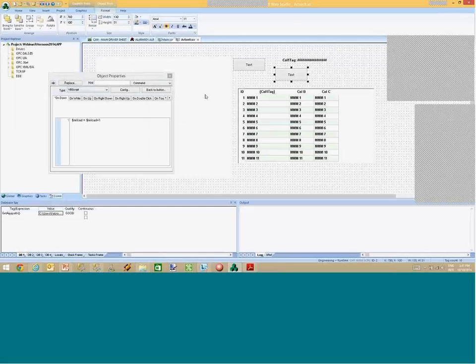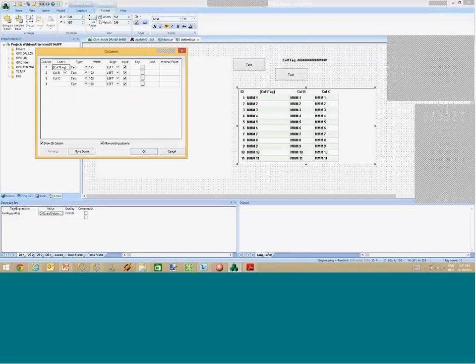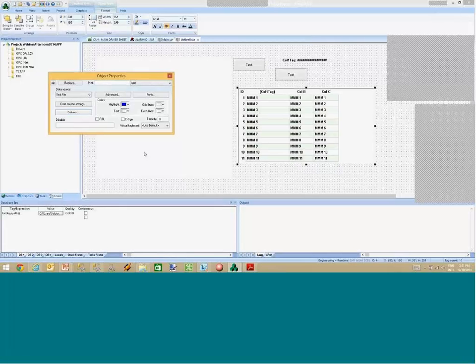So if I save it, if I have here in col one tag, let's say machine, toggle, it changes the label of this column to machine. If I change here col one tag to production, toggle, it changes the label to production. And if I change the value of col one tag to an empty string, the grid control automatically hides that column. So you can dynamically hide or show any columns from the grid control just by using string tags between curly braces in the label properties of the columns and manipulate the value of those string tags during the runtime. So that's pretty much a way to show or hide columns from the grid control during the runtime.